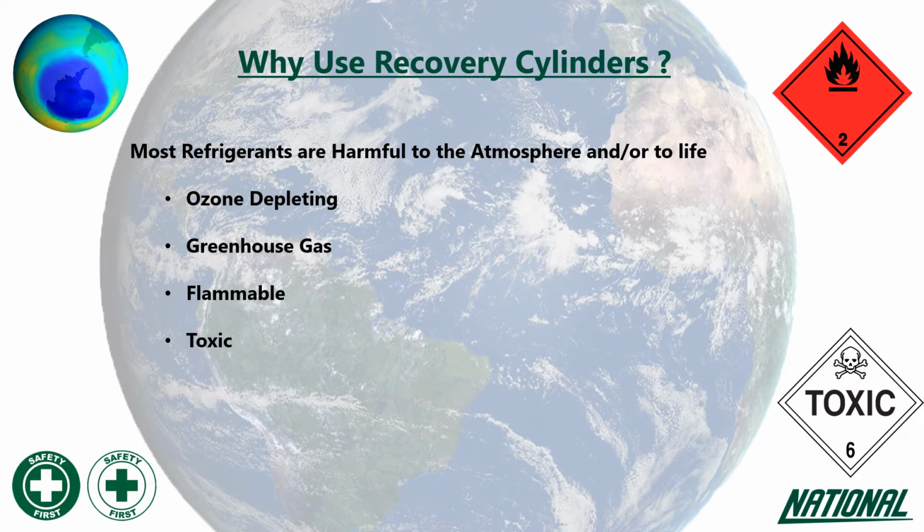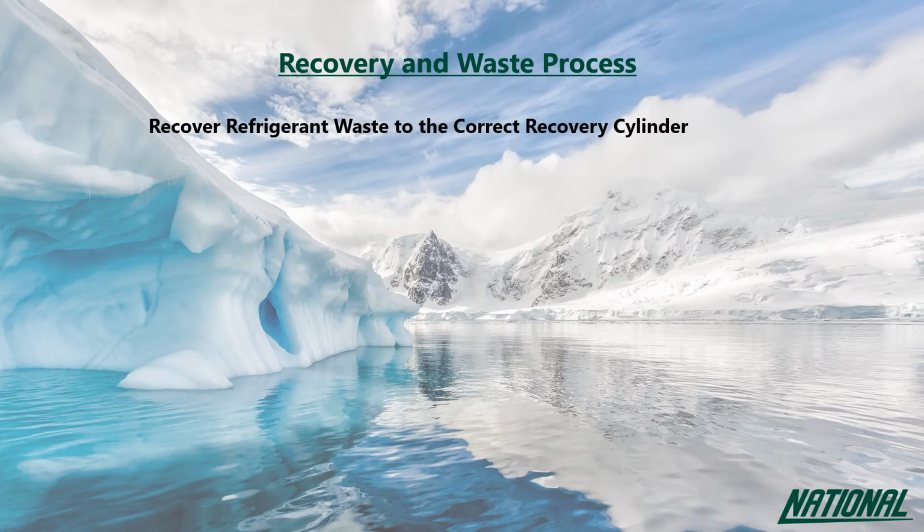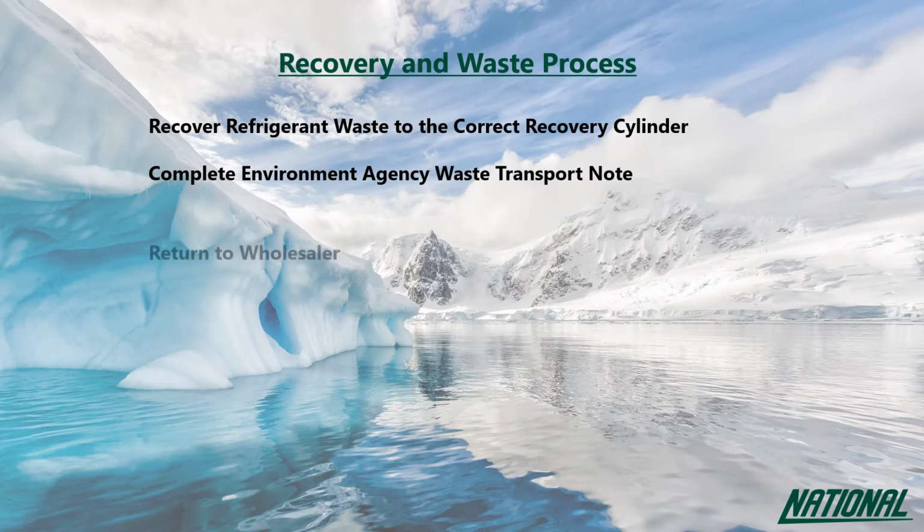And although CO2 is relatively harmless, if enough of it escapes, it can push all the air from the room, causing possible suffocation. When a refrigerant is no longer required, it is deemed as waste, and it is recovered to a recovery cylinder. The contractor must then complete an Environment Agency waste transfer note stating what refrigerant was recovered, where it was taken from, how much was recovered, and who recovered it, finishing with where is it going to. This is a legal requirement, and the cylinder cannot be transported without one.